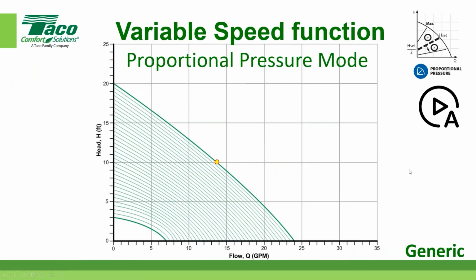Now let's look at proportional pressure. This is more the mystery mode. Same starting point here, but notice what the bouncing ball does as zones close in the system. It gets that little bump, and it's moving up and back down, up and back down. Notice it's going to a lower area potentially than if I had left it at constant pressure. So that's why we can confidently say this next statement: proportional pressure mode will be the most energy efficient mode of operation, hands down. However, if you don't have enough flow in the system and you're not heating adequately, you have shot yourself in the foot. That's why we want you to understand to get the right mode, so that you get the right flow under a design load condition. Hopefully that makes sense as well.